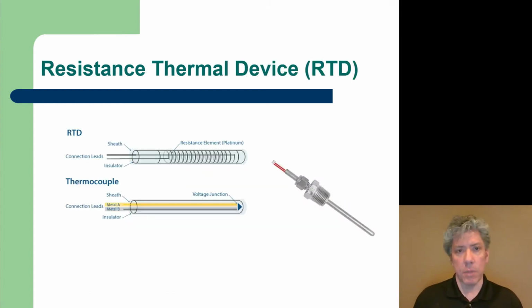On the other end of the spectrum are resistance thermal devices. These are very expensive, or relatively expensive, temperature measurement devices. Typically, the way these things work is they're essentially a resistor that depends on the temperature it's exposed to. And so the resistance element itself is usually made of platinum. That's part of what makes these devices so expensive. And they're most often covered with a sheath in order to protect them. So you see a picture of one there on the right. And they're much more expensive, but also more precise than a thermocouple. Now, typically a resistance thermal device cannot measure as wide a temperature range as a thermocouple.